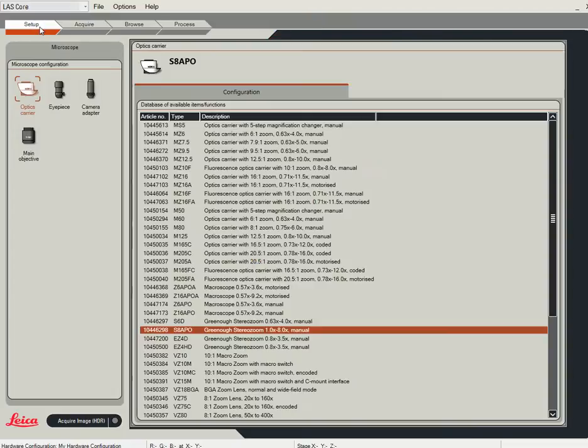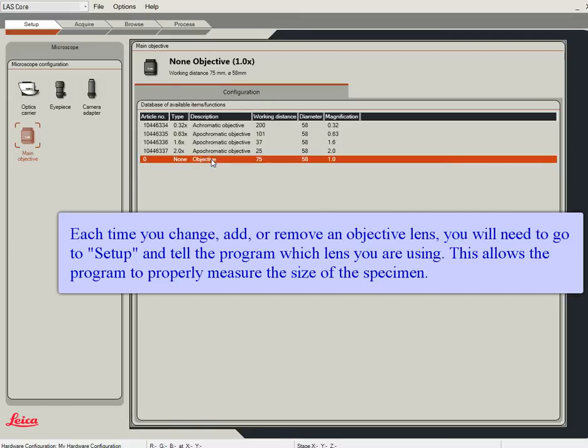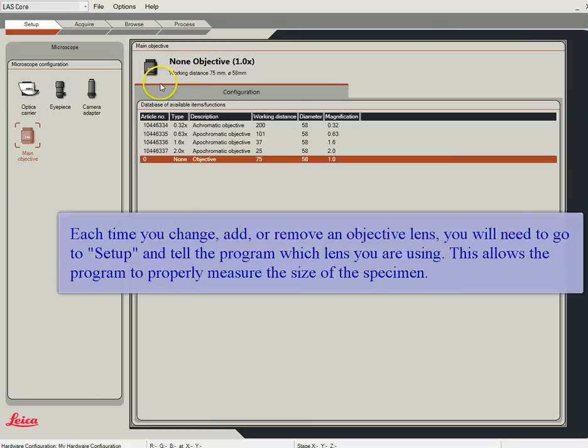So go to Setup. These first three things are constant, so they're already set up — this is the camera, the eyepiece, and the camera adapter. We're going to click on Objective. This is the one that you have to tell the microscope. Currently we don't have an extra objective on the scope and it says none, so objective is 1.0 — that's what we have set up.